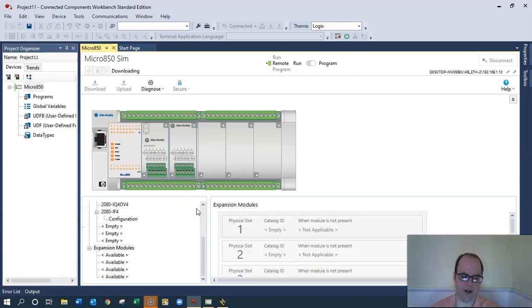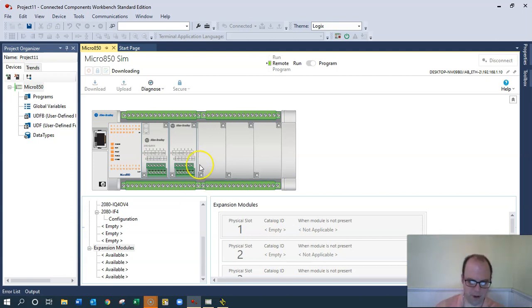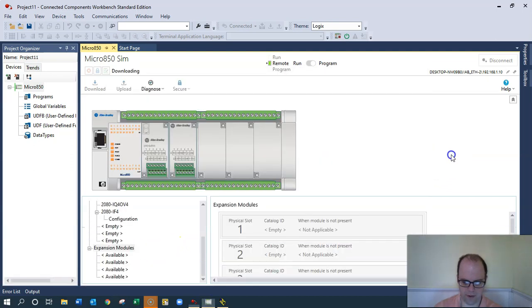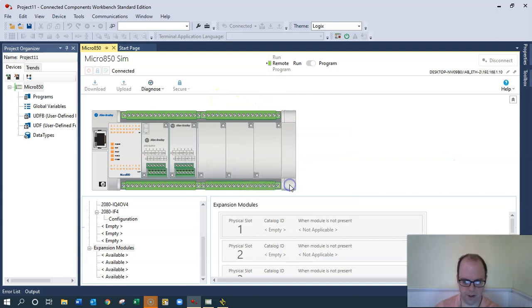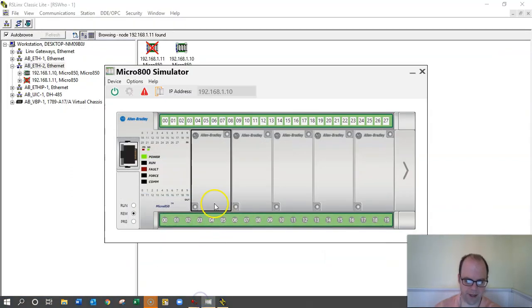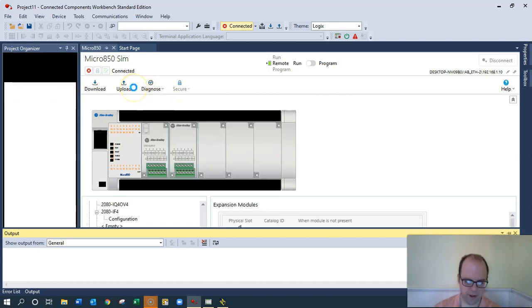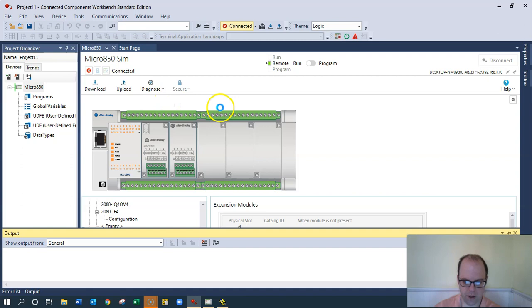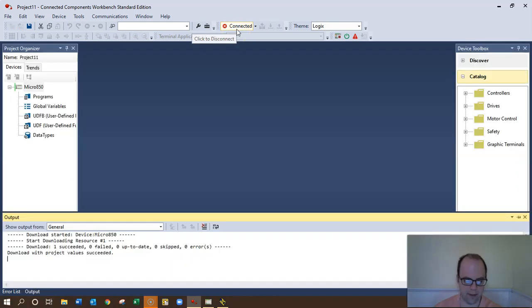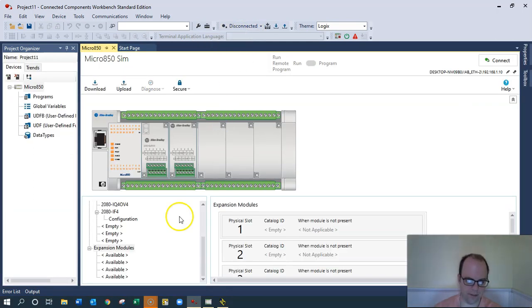Always download project values, because if you just download, maybe some of your values get reset to zero on accident. So always download with project values. Download successful. And look, it's giving me an error. Probably because the I.O. doesn't match up. So it's giving me a fault. And it's telling me there's a fault.